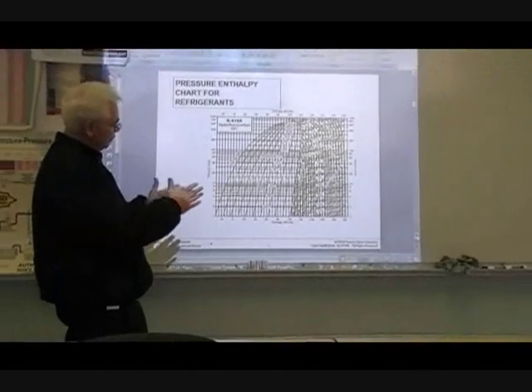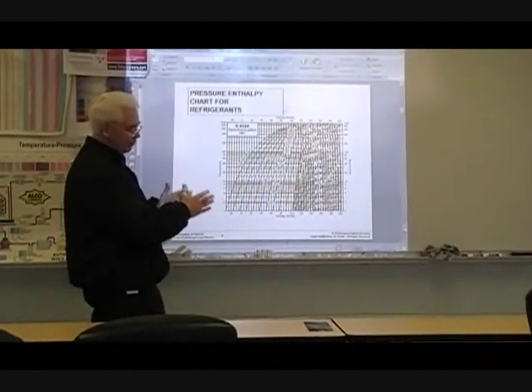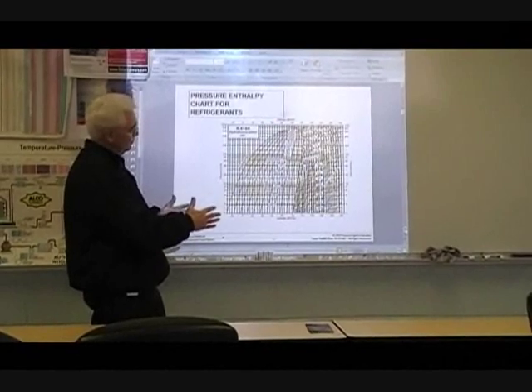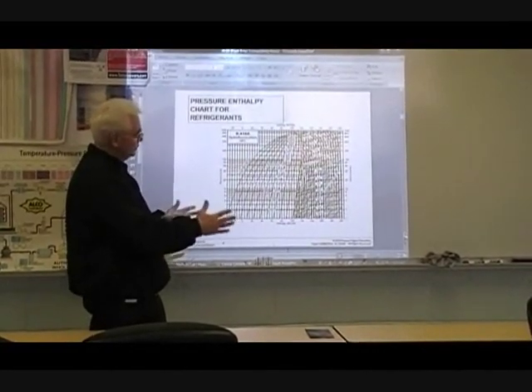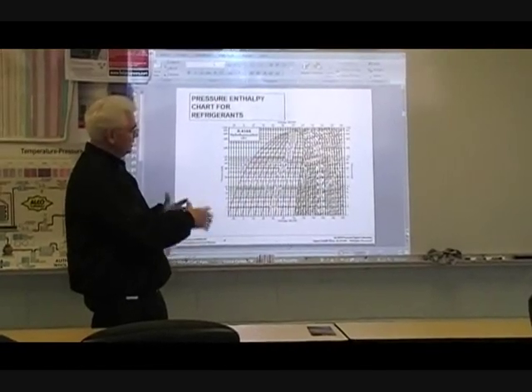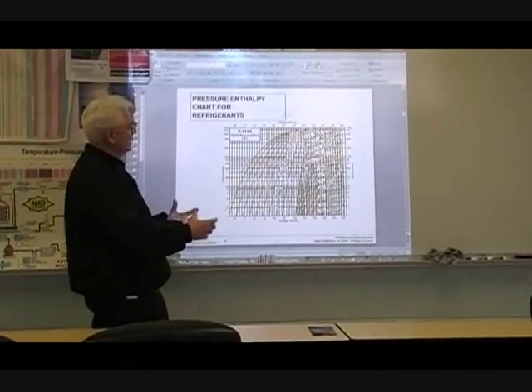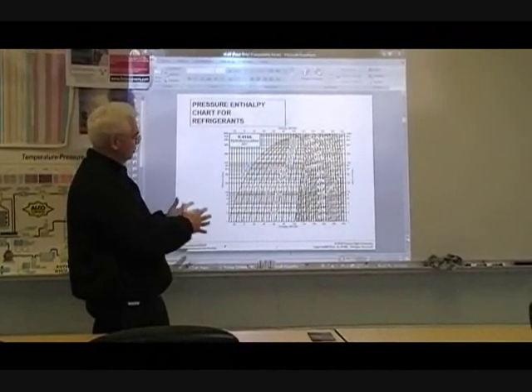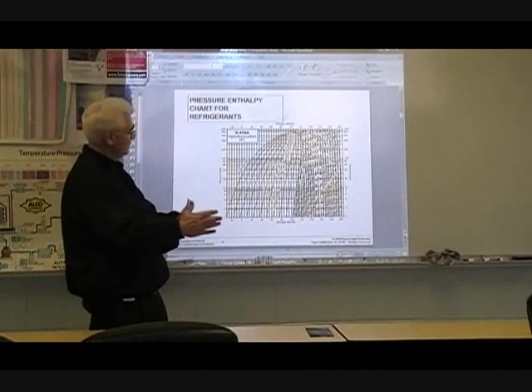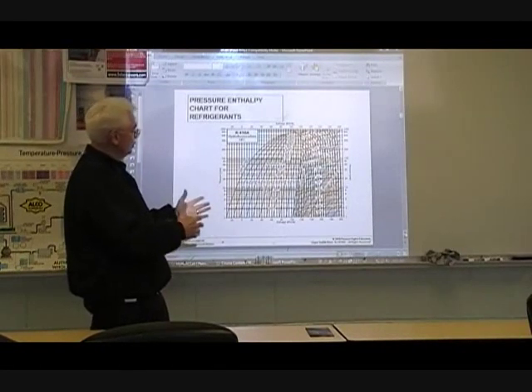It allows you to measure the amount of heat being removed in BTU per pound of refrigerant. You can measure usable refrigeration effect, which is what we call net refrigeration effect. You can measure your superheat, which is not part of the net refrigeration effect but is an important part of the system. You can measure the heat rejection, the heat of compression, and the effects that heat of compression and heat from the compressor motor has on the system.